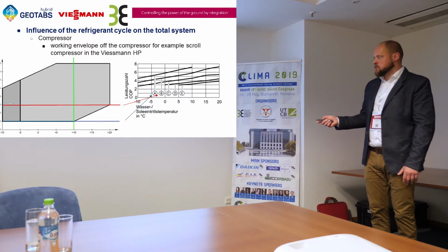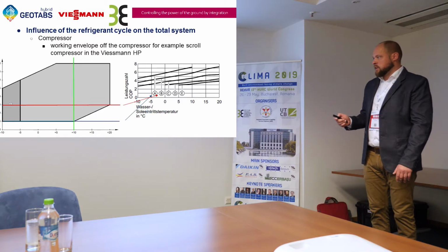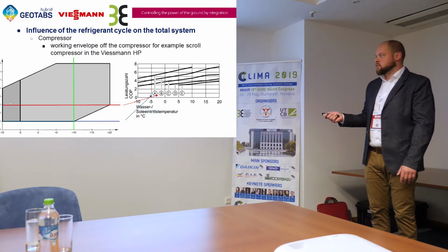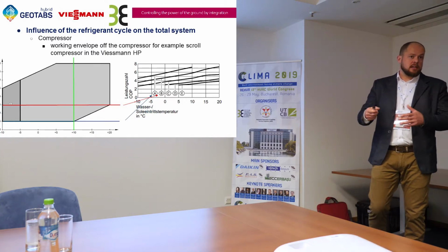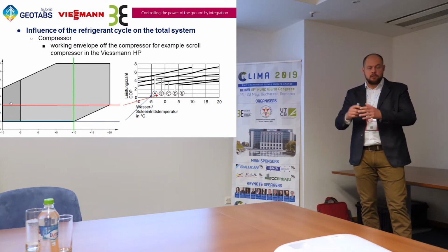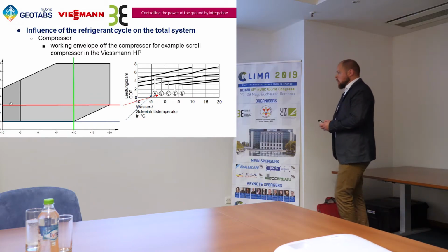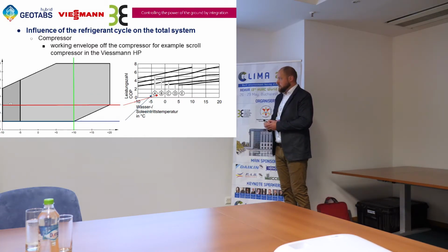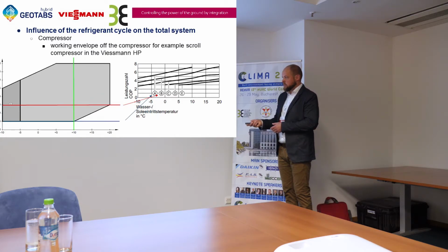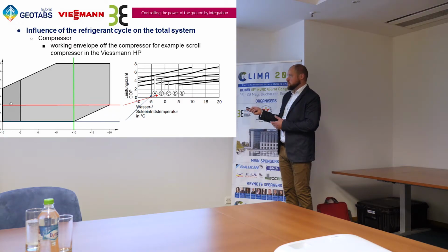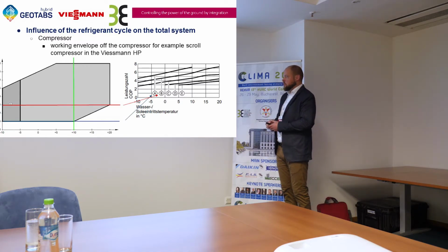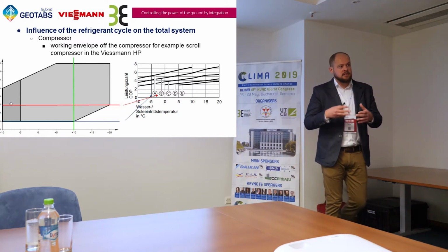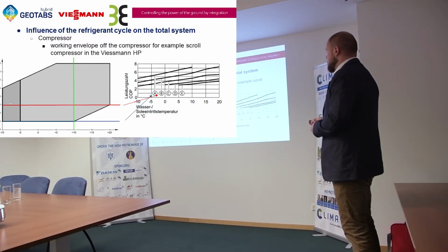So that's a bit the changing point. Higher than plus 10, the secondary temperature will rise, and we will have to find a solution, for example, work with a buffer tank so that we can keep the compressor running and regulate the temperature after that. Now, what's the influence of working in these temperature regions, 0 to 10 with a departing temperature of 25? This line you can see here. Above 0 degrees, we have a COP that's actually higher than 6. We go up to 6.5, 7 and more. So it's a very efficient working zone, but it has its effect on how we calculate the source side.